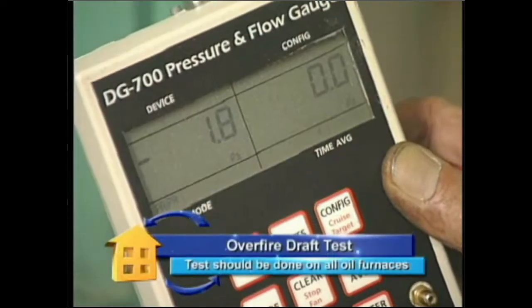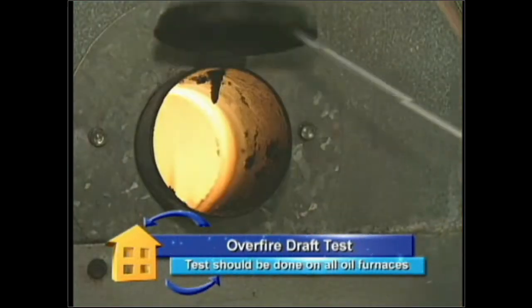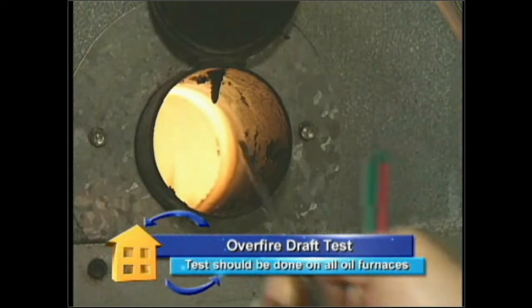And that probe is actually going into the burning chamber, right? It goes into the burning chamber. And the reason we want to measure that over-fire draft is these things pull a massive amount of air in draft. They pull about 10 to 15 pascals. Wow, that's a lot more than a gas furnace. Yep, a lot more than gas.